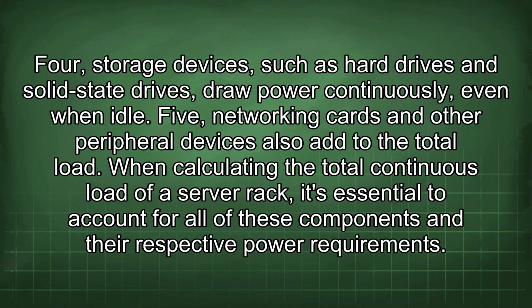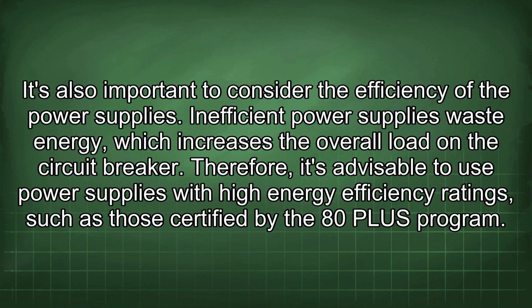When calculating the total continuous load of a server rack, it's essential to account for all of these components and their respective power requirements. It's also important to consider the efficiency of the power supplies. Inefficient power supplies waste energy, which increases the overall load on the circuit breaker. Therefore, it's advisable to use power supplies with high energy efficiency ratings, such as those certified by the 80+ program.